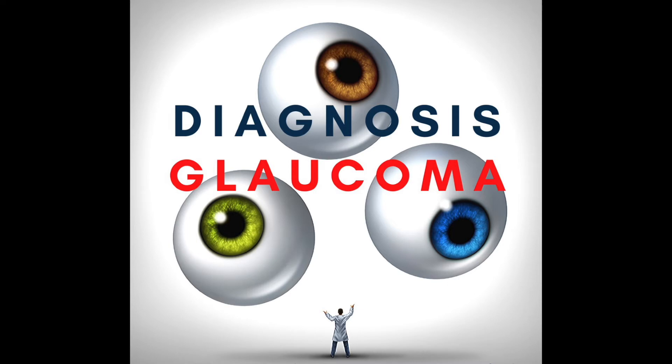With the Eye Care and the home device — you talked about how they work — how are they different from other devices that check eye pressure? The main difference is in the requirement of topical anesthesia, which the Eye Care doesn't require. Another thing that sets it apart is that it's not as impacted by the shape of the cornea. Sometimes, if a patient has a history of corneal disease or corneal surgery, the applanation tonometer is not as reliable at getting a pressure, whereas the Eye Care is not as dependent on this.